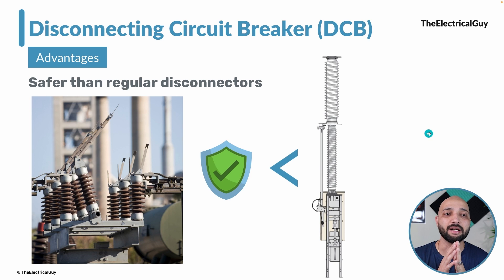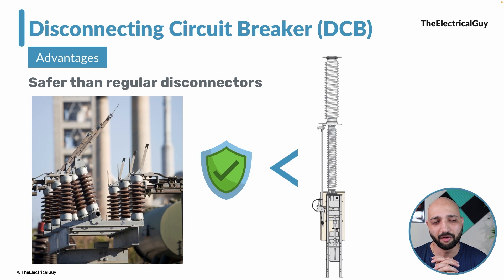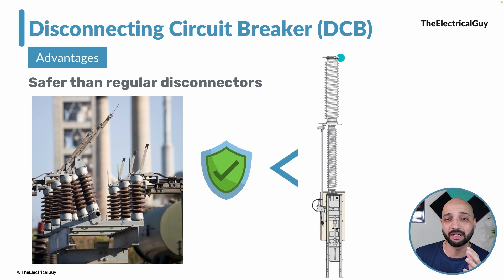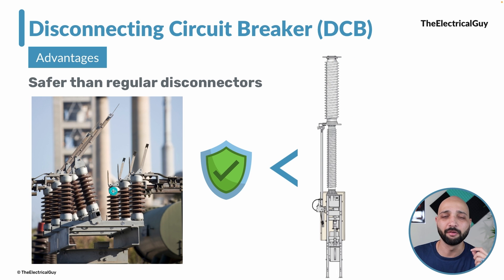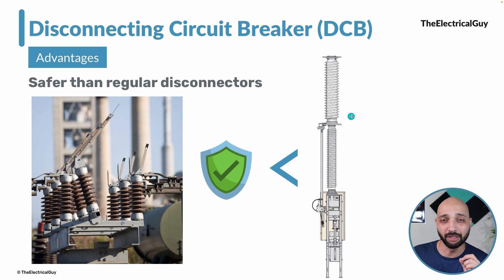The next advantage is that these are safer than regular disconnectors. Air-insulated disconnectors are not as safe when compared to a disconnector function performed inside the interrupter filled with SF6 gas. Arcing and sparking that normally happens when opening a disconnector is completely eliminated with the disconnecting circuit breaker, making it definitely superior from a safety aspect.